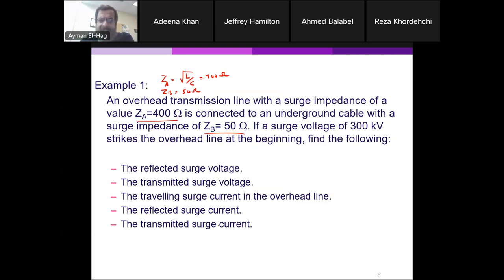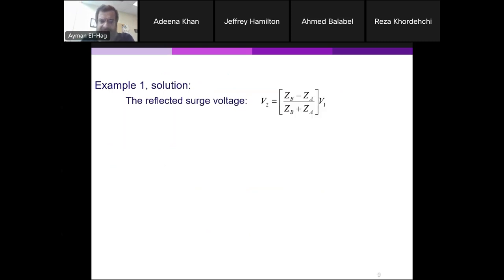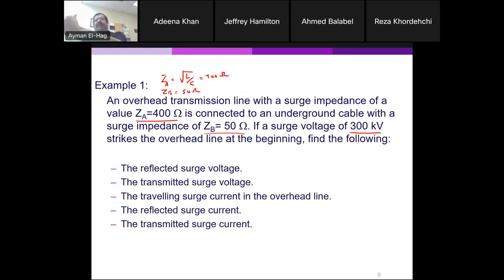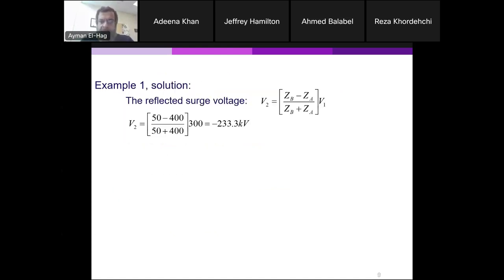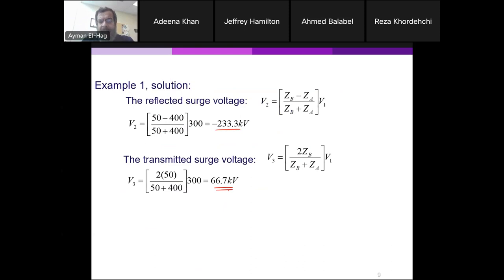So we want to see different things here. Now we have a surge of voltage 300 kilovolt that strikes the overhead line at the beginning. Find the following different things. So the reflected surge is equal to this. Okay, this is how much is reflected back. Now we have ZB less than ZA, so the reflected wave will be negative, which is a good thing because now it will actually be reducing the incident wave. So just substitute 50 minus 400 over 50 plus 400 times 300, so you get minus 233 kilovolt. That is how much is reflected back. The transmitted surge is basically V3, times 2ZB over ZA plus ZB, this is the refraction coefficient, and you will find that this is equal to 66.7.